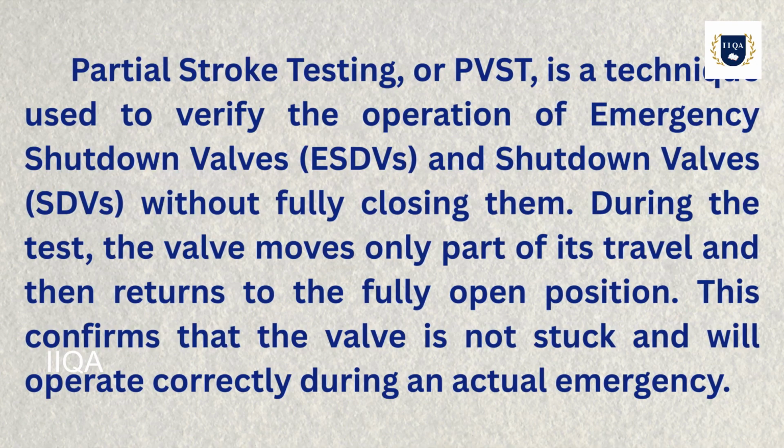Partial stroke testing, or PVST, is a technique used to verify the operation of emergency shutdown valves, ESD and shutdown valves, SD, without fully closing them. During the test, the valve moves only part of its travel and then returns to the fully open position. This confirms that the valve is not stuck and will operate correctly during an actual emergency.